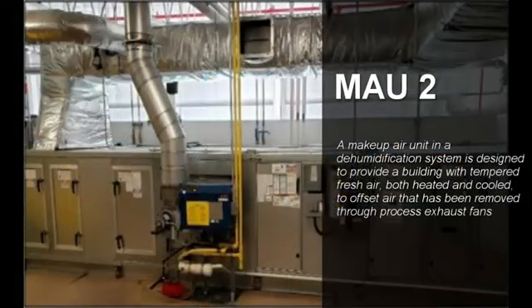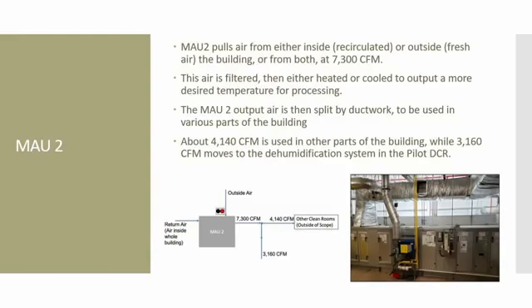So it is important to understand the function of the system components. A makeup air unit in a dehumidification system is designed to provide a building with tempered fresh air, both heated and cooled, to offset the air that is being removed through process exhaust fans inside of the conditioned space, which in this case would be the pilot dry clean room. So the MAU2 is the first unit the intake air goes through. It pulls in air from either inside or outside the building, or from both at 7,300 CFM, based on the schedule provided by Clarios. This air is then filtered to remove particles. The air is either heated or cooled to output a more desired temperature for processing.